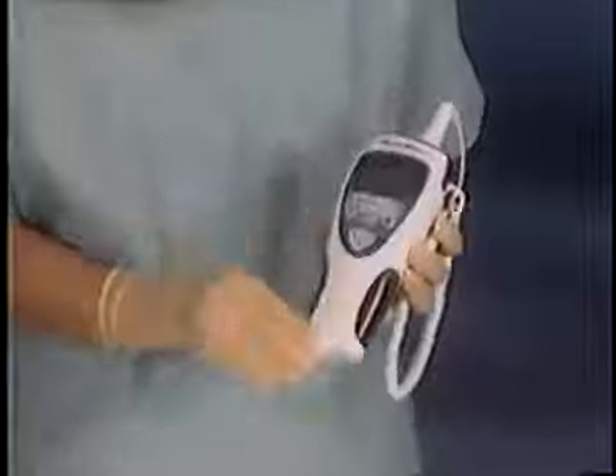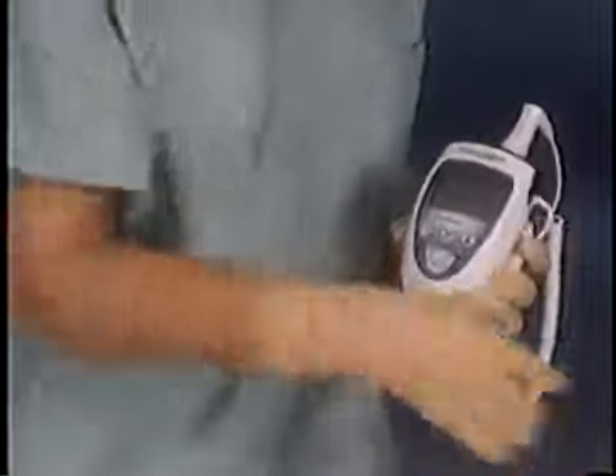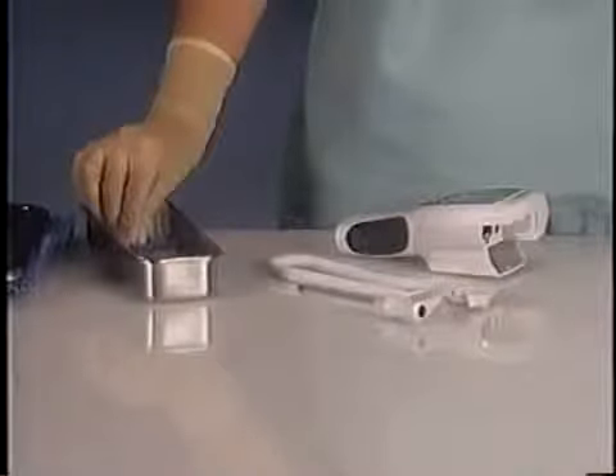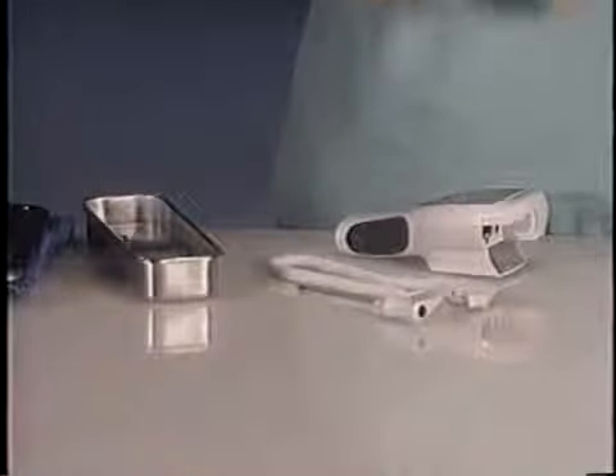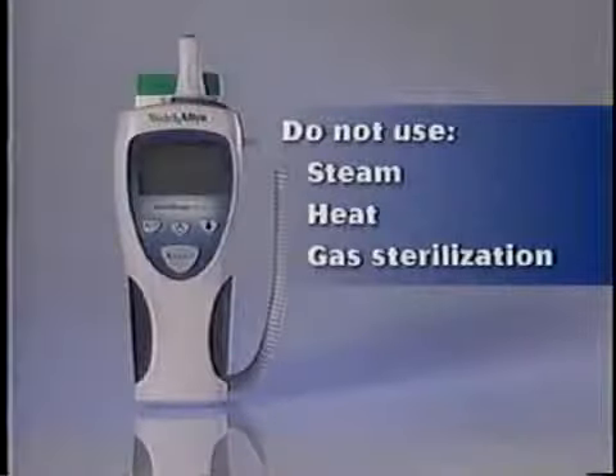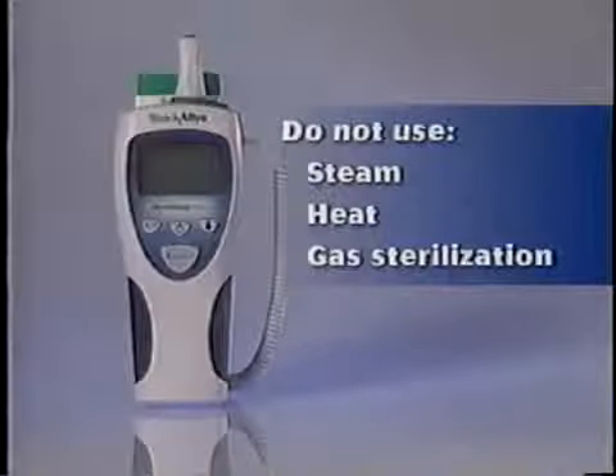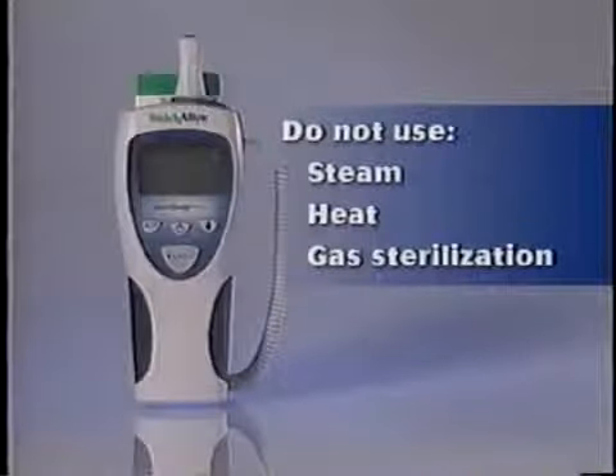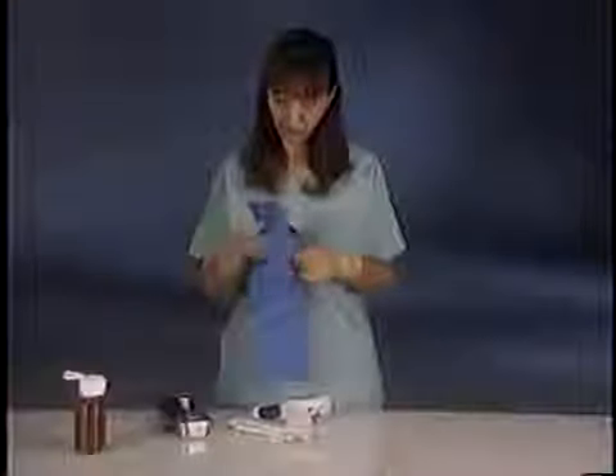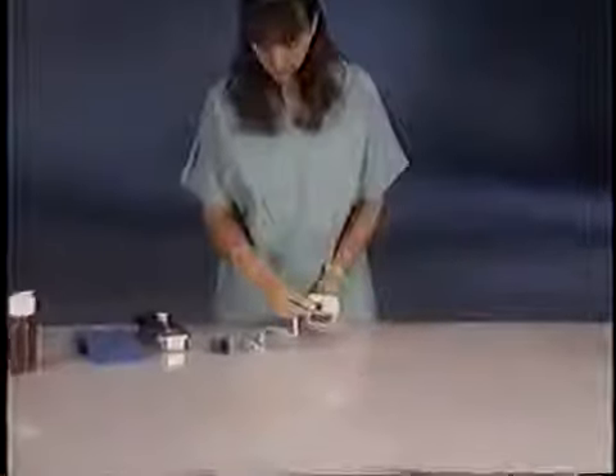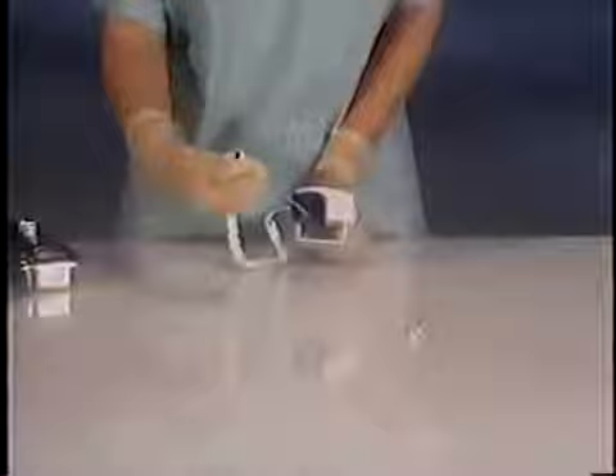Avoid soaking the thermometer or probe in any type of fluid. You can, however, place the probe well in mild detergent solution for cleaning. Do not use steam, heat, or gas sterilization on any of the SureTemp Plus components. Dry all surfaces thoroughly before reassembling the thermometer. Reconnect the probe. Reinstall the probe well and place the probe back in the well.